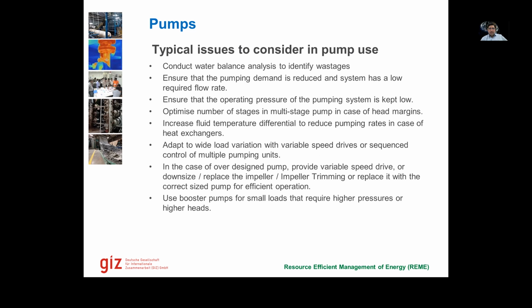Yeah, then water balance analysis would also show us where the whole water is coming in. Sometimes we've seen that companies use dampers and bypass lines. So if the water is not required on the demand side, they bypass the line and the water goes back to the suction tank, which is a total loss of efficiency. Instead, variable frequency drives should be installed. Variable frequency drives pretty much work more than 50% of the time.